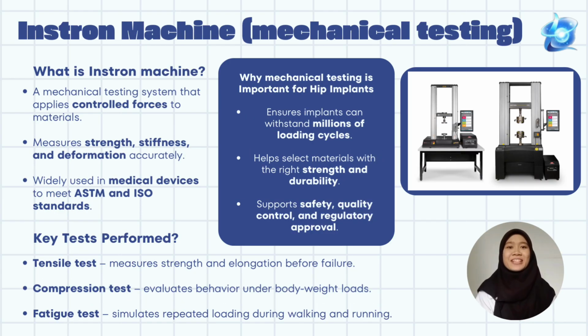The Instron machine is a mechanical testing system used to apply controlled forces to materials. It measures properties such as strength, stiffness, and deformation through tensile, compression, and fatigue tests. These tests simulate real-life loading conditions experienced by hip implants inside the human body. The Instron machine ensures implant materials can withstand repeated loads, supporting safety and quality standards.